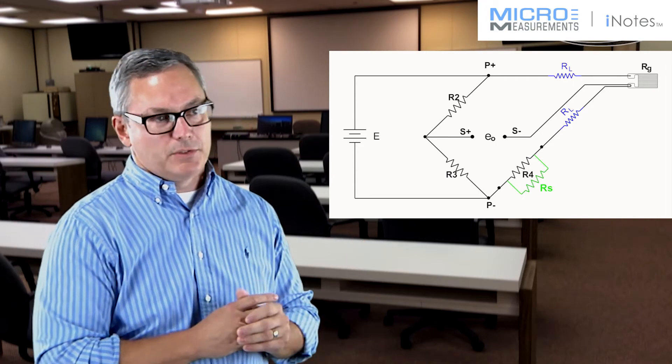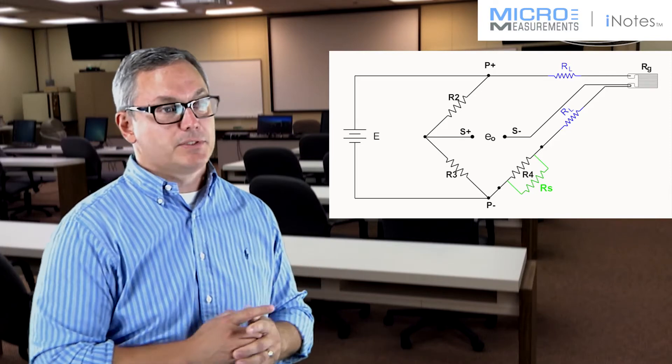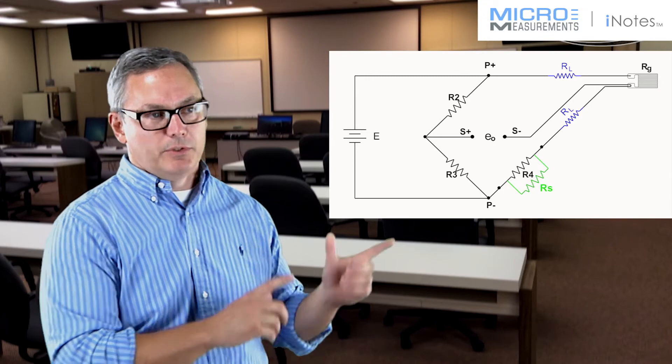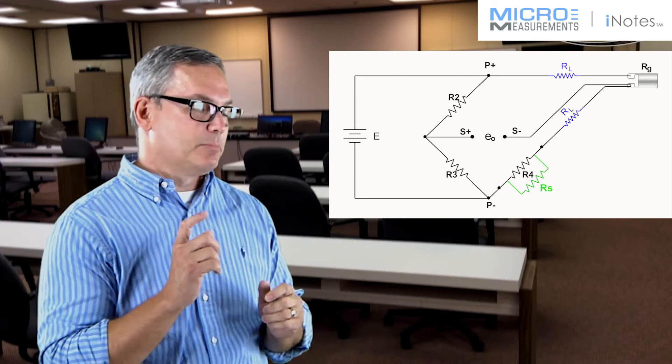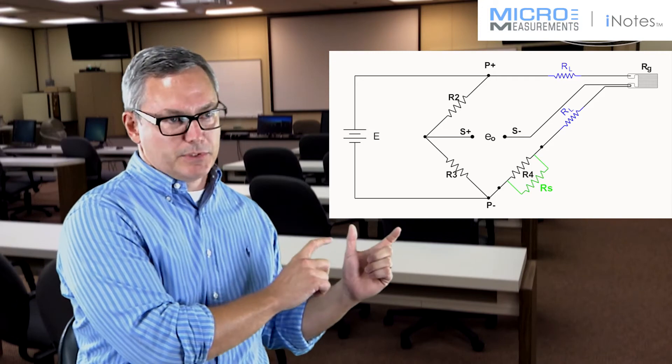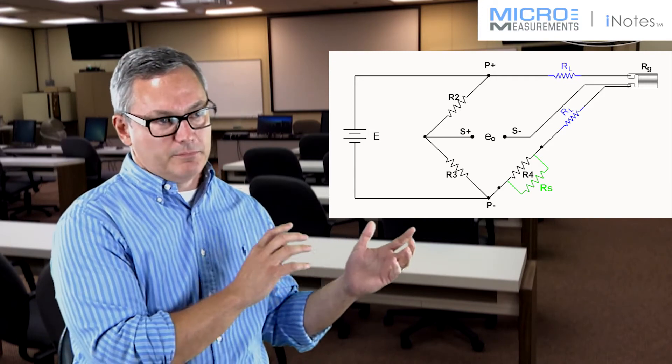One of the advantages to shunt calibrating the dummy resistor is that you can use it to compensate for the lead wires that are connected to your strain gauge. In addition, when you shunt the dummy resistor, you're taking a precise resistor and connecting it across another precision resistor, and that simulates a very precise level of change.